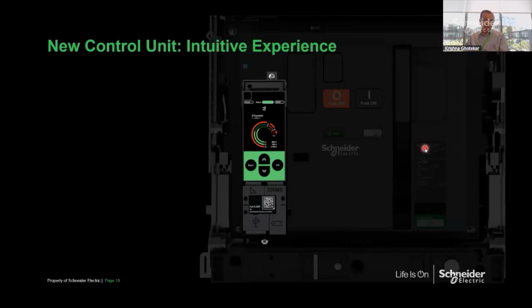for a project. So for example, all the trip units, whether it's A, E, AP, or EP, come with NFC communication. NFC is near field communication, which means even if there is no power inside the circuit breaker, I can just take my smartphone and tap it close to the trip unit, and it can communicate. That makes troubleshooting easier, to know the type of the fault, as well as to do the power restoration once I get the complete diagnostic. So you don't need power inside the circuit breaker to connect using NFC.